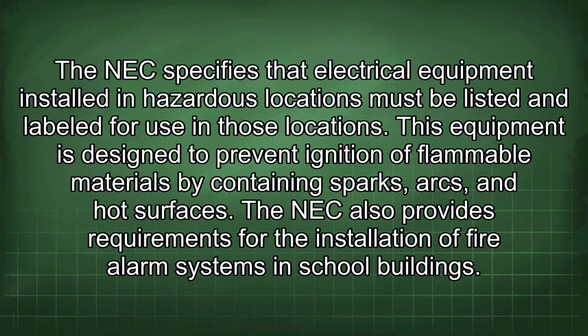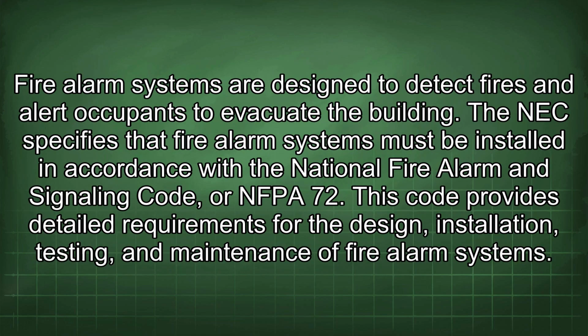The NEC also provides requirements for the installation of fire alarm systems in school buildings. Fire alarm systems are designed to detect fires and alert occupants to evacuate the building. The NEC specifies that fire alarm systems must be installed in accordance with the National Fire Alarm and Signaling Code, or NFPA 72. This code provides detailed requirements for the design, installation, testing, and maintenance of fire alarm systems.